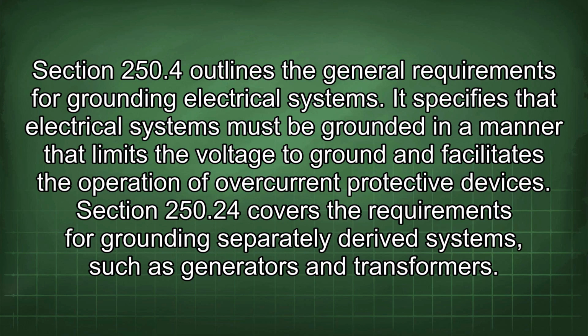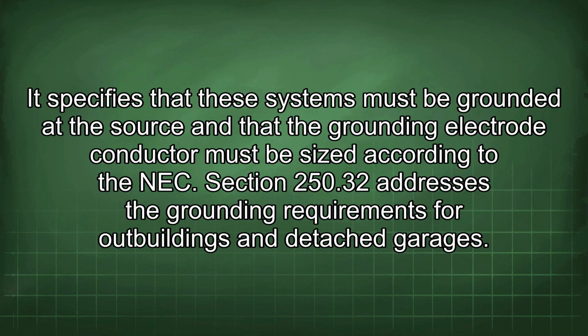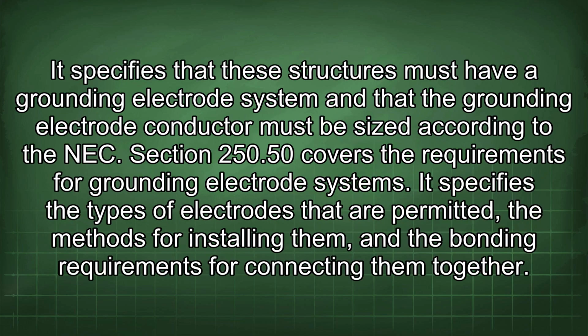Section 250.24 covers the requirements for grounding separately derived systems such as generators and transformers. It specifies that these systems must be grounded at the source and that the grounding electrode conductor must be sized according to the NEC. Section 250.32 addresses the grounding requirements for outbuildings and detached garages. It specifies that these structures must have a grounding electrode system and that the grounding electrode conductor must be sized according to the NEC. Section 250.50 covers the requirements for grounding electrode systems. It specifies the types of electrodes that are permitted, the methods for installing them, and the bonding requirements for connecting them together.